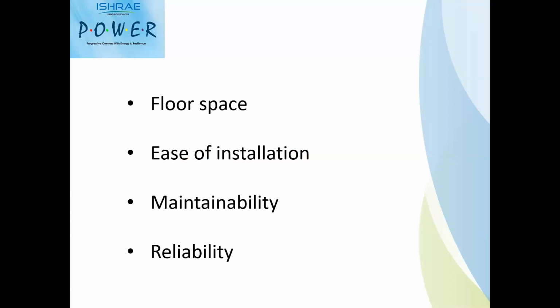Then ease of installation. The pump should be very easily installable, where we can quickly finish it off and make installation very simple. Maintenance wise, as the building owner has to maintain these pumps for a lifetime, maintenance should be very minimal whenever we are selecting a particular pump. And then of course reliability, where the life of the pump should be long, which will give you good results in terms of the operation of the building.